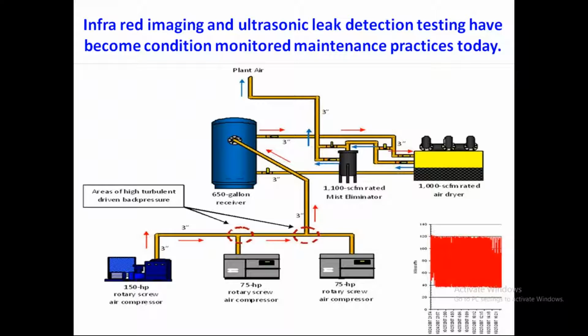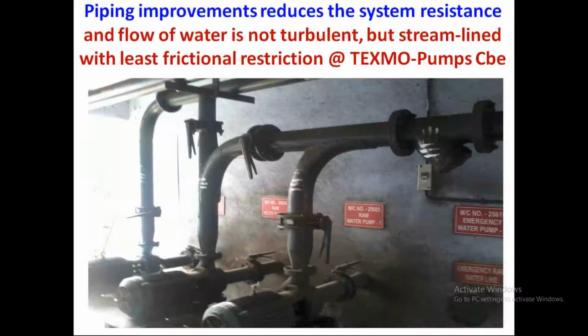Where you find the T connection, that is a point of turbulence. Many industries have replaced their T joints in the compressor house with these conjoining joints. I'll just show you the conjoining joint. This is on a water pipe, but the same thing can be done on an air pipe also. They have to go for 45-degree conjoining bends on the compressed air header. Straight away, it can give a minimum of 5 to 10% savings, depending on the turbulence happening in the T joints in the compressor house.